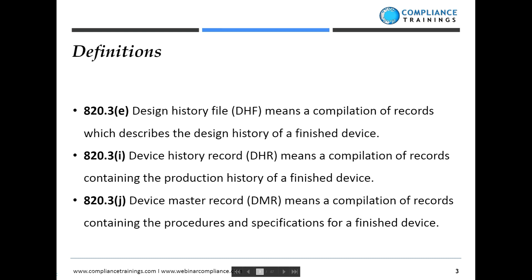A few definitions: the Design History File is a compilation of records that describes the design history of the finished device. We'll talk about what the agency's final rule says about what's included and not included in the Design History File. The Device History Record is developed out of the Design History File work and demonstrates that production was made in accordance with the Device Master Record, which is compiled through the transfer process into production. The Device Master Record is a compilation of all the procedures and specifications for the finished device.